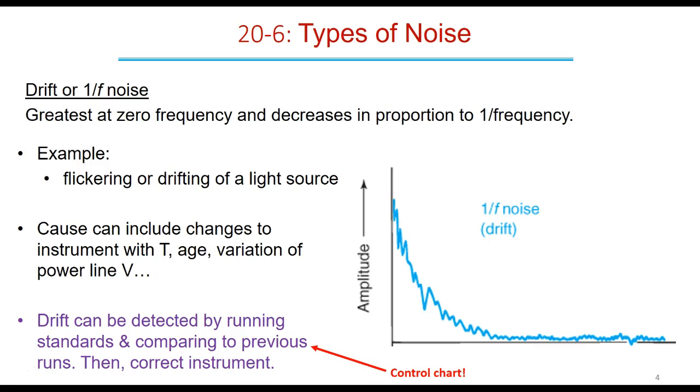Now this is how you know that this is going to happen: you're going to use a control chart. In a UV-vis spec, or in any kind of spectrometer with some type of source, you're going to control that by tracking its output over time. You can do this by tracking lamp hours, or how much time it's on. A lot of instruments will actually, when you put in a new lamp, let you say, hey, start tracking, and every time the instrument's on, it'll track the hours.